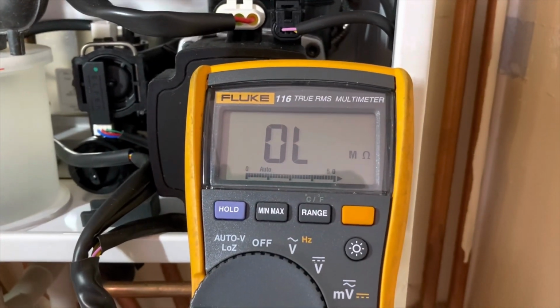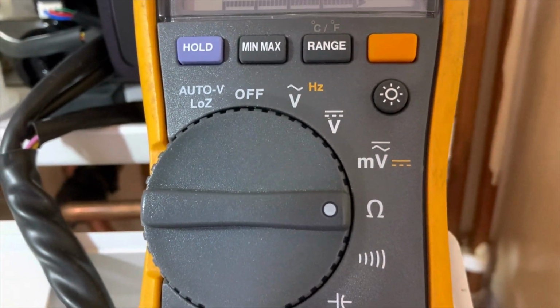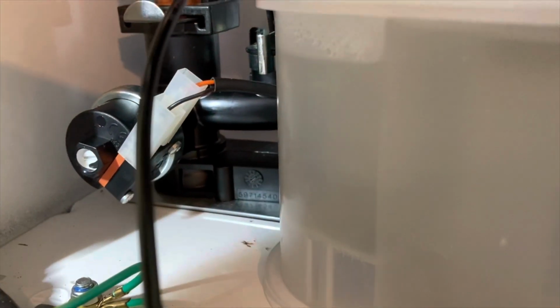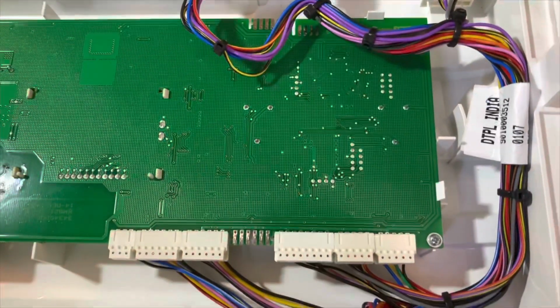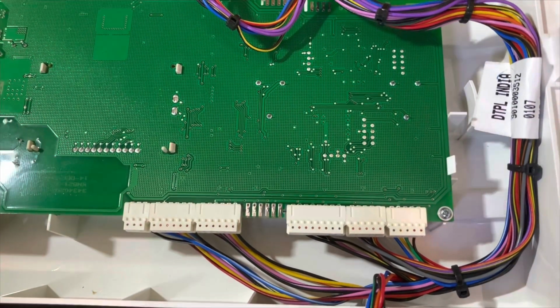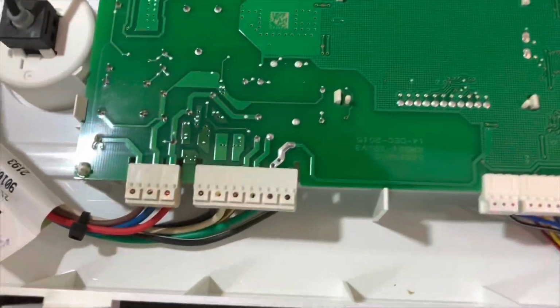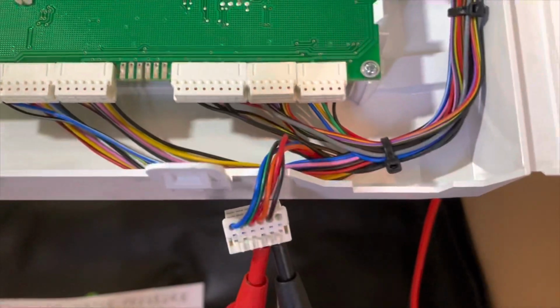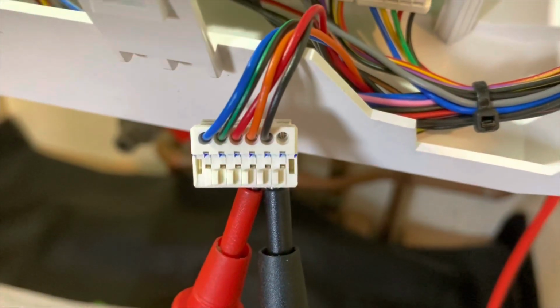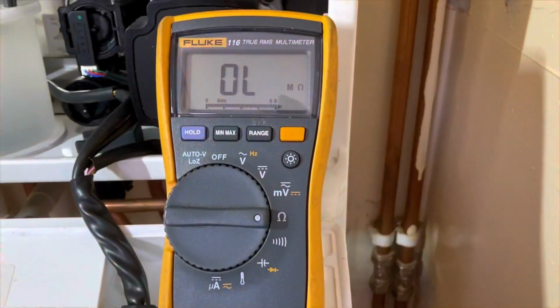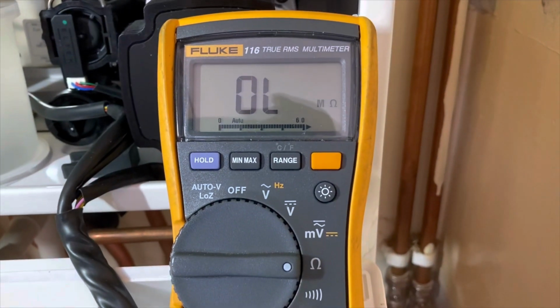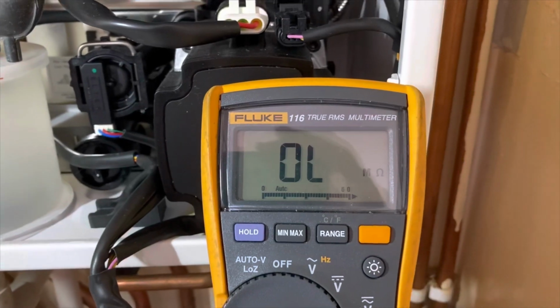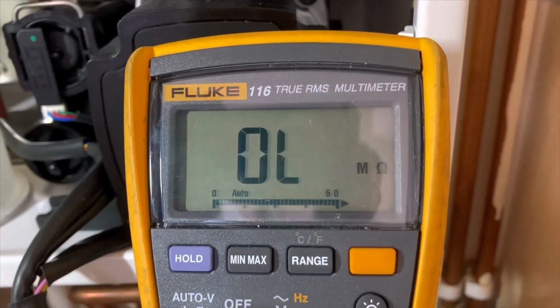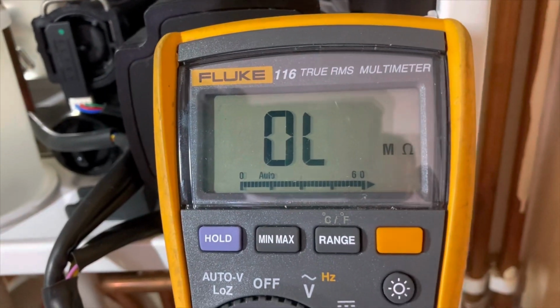Okay, as you can see here, I've got my multimeter set to ohms. I've found the pressure switch, which is this here. You can see the black and orange cable. I've accessed the circuit board. I've found the low voltage side of the circuit board. Again, you can see the connections are smaller compared to the mains voltage, and the mains voltage cables are thicker. The low voltage cables are thinner. I've found the orange and black here. I've connected my multimeter up to it, and because before, when you saw the front of the boiler, it had 0 bar of pressure in it, and it came up with an F1 fault code. Now we're reading OL. There's literally no water in the boiler, so the circuit is open.